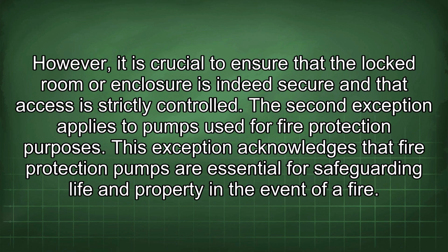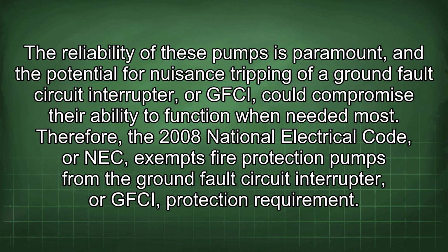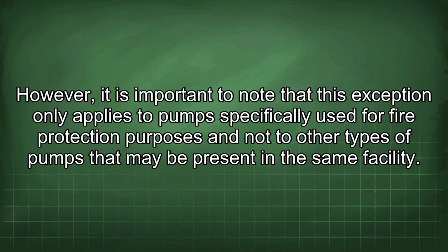This exception acknowledges that fire protection pumps are essential for safeguarding life and property in the event of a fire. The reliability of these pumps is paramount, and the potential for nuisance tripping of a GFCI could compromise their ability to function when needed most. Therefore, the 2008 NEC exempts fire protection pumps from the GFCI protection requirement. However, it is important to note that this exception only applies to pumps specifically used for fire protection purposes and not to other types of pumps that may be present in the same facility.